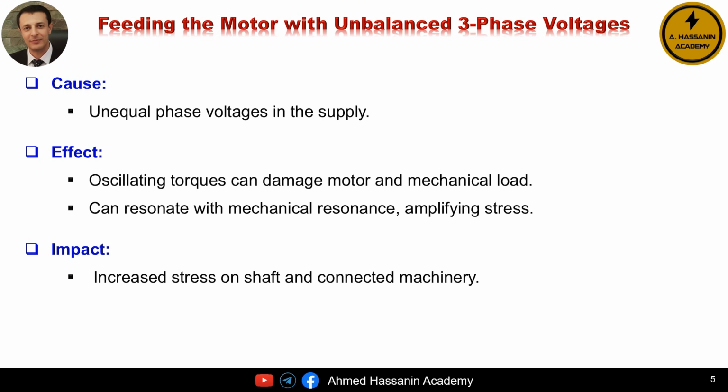That wobbling torque puts stress not only on the motor itself, but also on whatever machinery it's driving. And here's an interesting point. These oscillating torques can sometimes resonate with the mechanical vibrations of the machine. Resonance is like when you push someone on a swing at just the right rhythm, it makes the swing go higher. In the motor, this resonance amplifies the stress, which can be really damaging if not controlled. The end result?